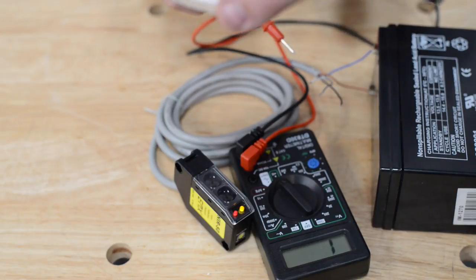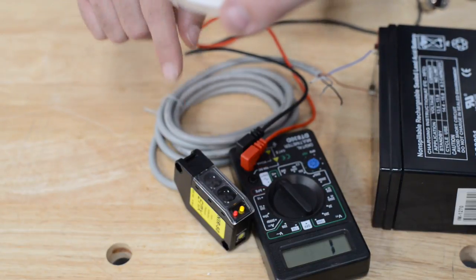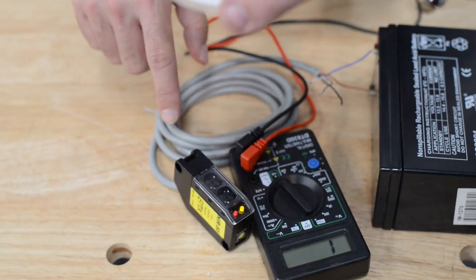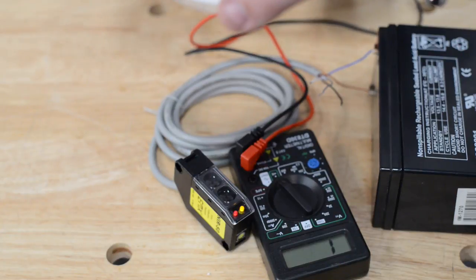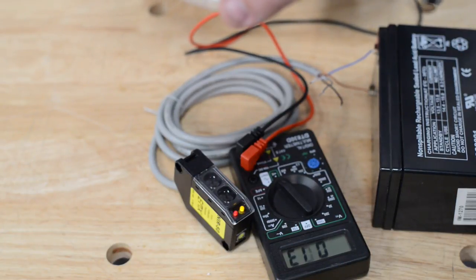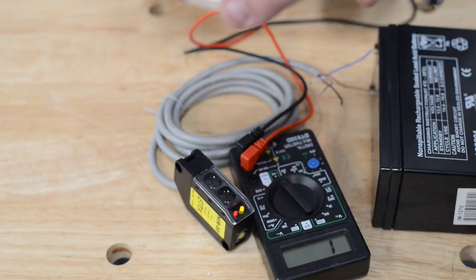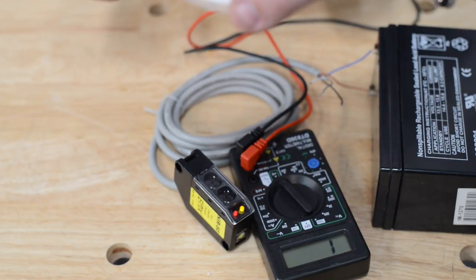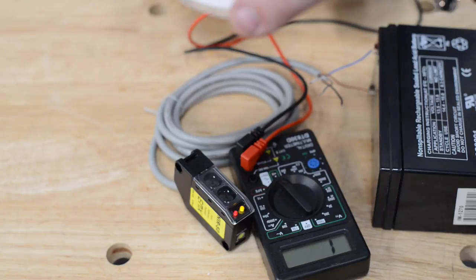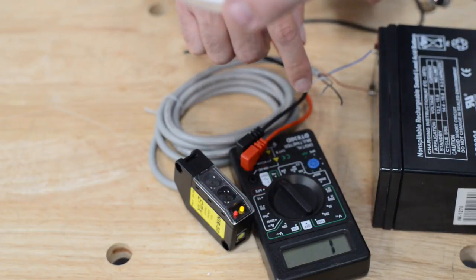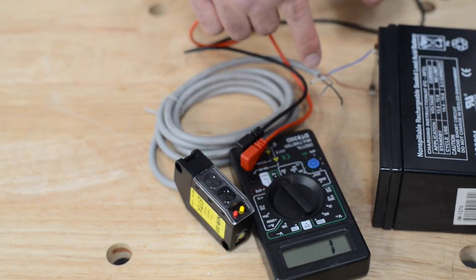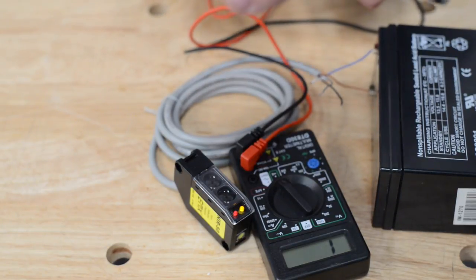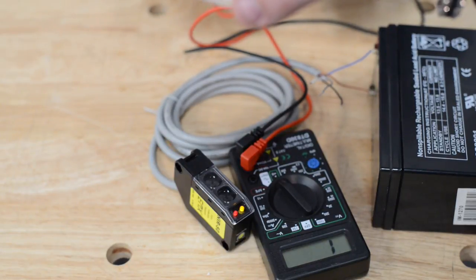And again, the reason I found this out was with the beam connected, meaning this in its default state, my expectation is the normally closed will be closed and the normally open will be open. So I was looking for continuity. I started with the white and the gray. I did not have continuity indicating one was going to be common and one is going to be normally open.